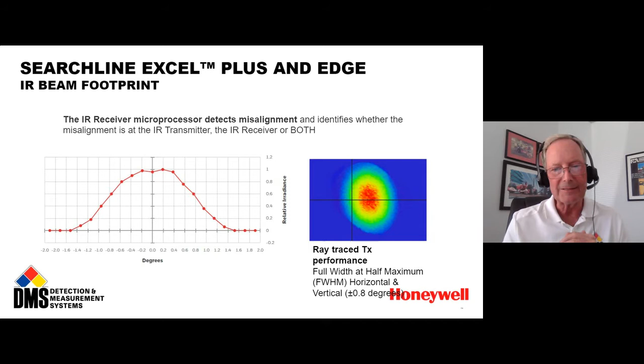What's also immensely clever about this is that we're projecting the IR beam from the transmitter to the receiver. And in this illustration here, we have perfect alignment where we're centered, focused on the high intensity portion of the beam. Over here on this illustration, the IR transmitter is misaligned, and the more intense portion of the beam is not aligned properly with the receiver. In this case, the beam from the transmitter is aligned correctly, but the IR receiver is misaligned. The smarts that have been built into the microprocessor that monitor the alignment are not only able to tell the customer that there is misalignment in these cases where misalignment occurs with one or other end of the system, but it's able to tell you whether it's the IR receiver or the IR source that's misaligned, or both.